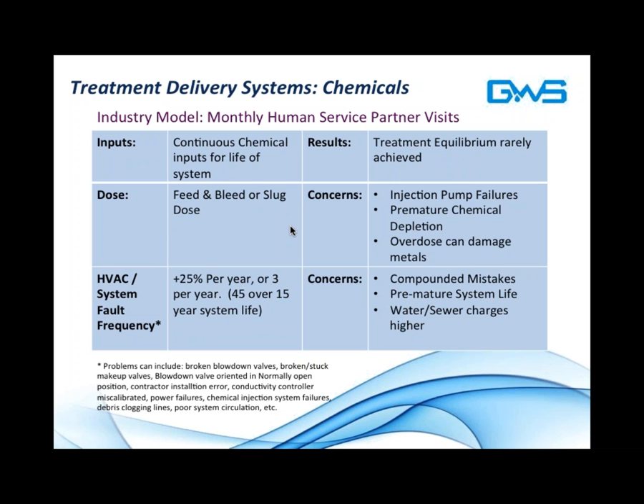And let's talk a little bit about HVAC system fault frequency, because what I'm talking about here now is not necessarily the fault of the service partner. It is simply the fact that cooling systems are complicated systems. There are multiple moving parts, such as blowdown valves, makeup valves, pressure, temperature sensors, many moving things. There's fill, there's variable speed drives, a whole bunch of things within a cooling system. Inevitably, as multiple chemical service partners have told me, there will be, in a given year, 25% of all of the service partners' jobs experiencing some kind of hiccup. Again, this is not necessarily due to the chemical injection failure, but it's more likely due to a broken makeup valve, a broken or a stuck discharge valve, a blowdown valve, for example. And these things happen all the time.